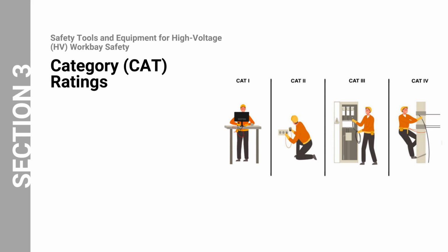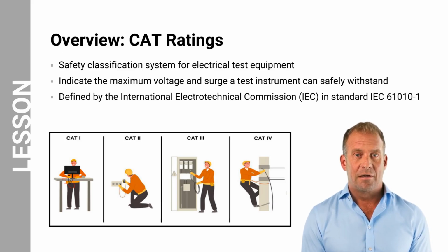Now we will cover the various category ratings, also commonly known as CAT ratings, for electrical test equipment. CAT ratings are a safety classification system for electrical test equipment. They indicate the maximum voltage and transient overvoltage, or surge, that a test instrument can safely withstand. CAT ratings are defined by the International Electrotechnical Commission in Standard IEC 61010-1. There are 4 CAT ratings, from CAT 1 to CAT 4, each corresponding to a different level of electrical hazard. A category rating of a test instrument defines where in the electrical supply chain it can be safely used. We will explain the ratings in detail as we move ahead.